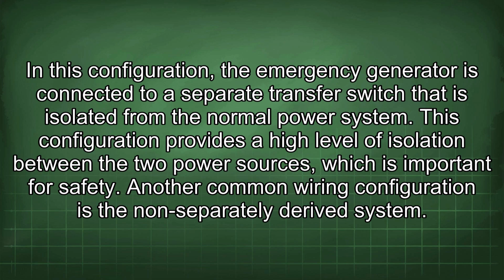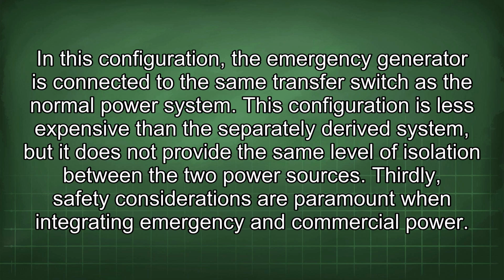Another common wiring configuration is the non-separately derived system. In this configuration, the emergency generator is connected to the same transfer switch as the normal power system. This configuration is less expensive than the separately derived system, but it does not provide the same level of isolation between the two power sources.